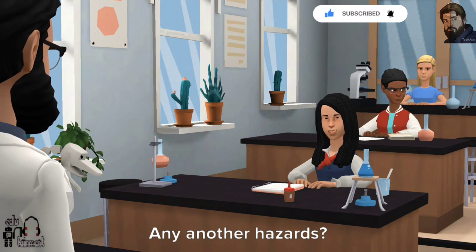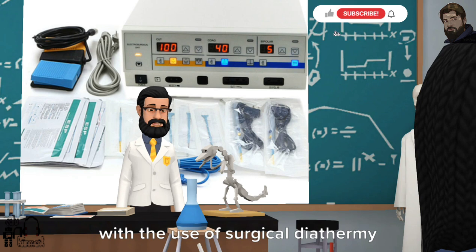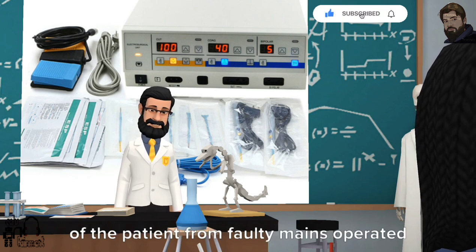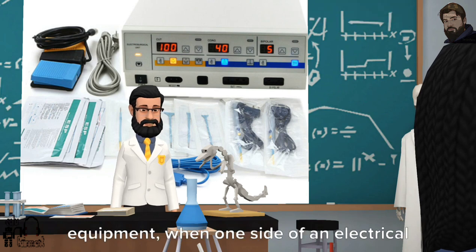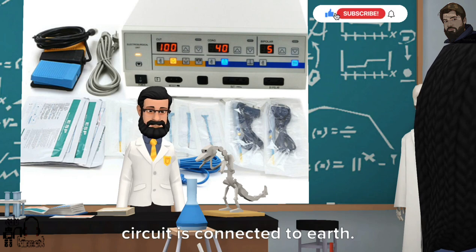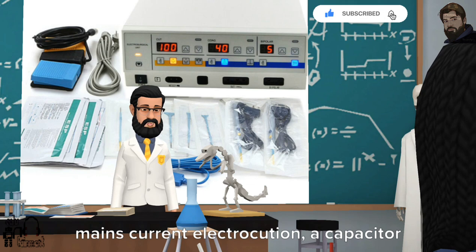Any other hazards? Another serious hazard associated with the use of surgical diathermy machines is the possible electrocution of the patient from faulty mains-operated equipment when one side of an electrical circuit is connected to earth. In order to provide protection against mains current electrocution, a capacitor RF earthed is generally included between the indifferent lead and earth.